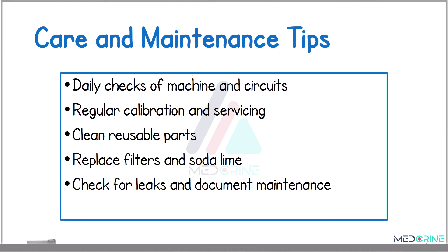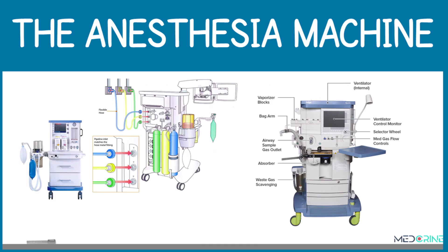Care and maintenance tips for the anesthesia machine include a daily check of the machine's circuits, regular calibration and servicing, regular cleaning of reusable parts, replacement of filters and soda lime, and checking for leaks and documentation of the maintenance schedule. These practices are essential for keeping the anesthesia machine reliable and safe to use.